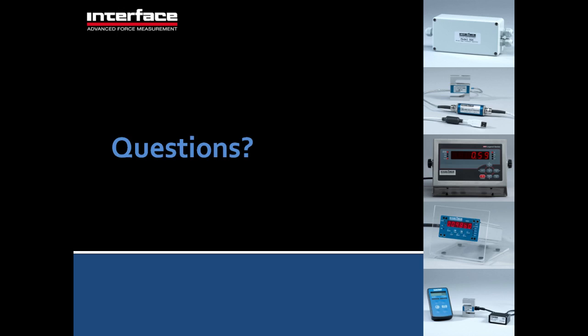And how do you know what sample rate is required? It's hard to say. Typically it's not going to be totally obvious, but typically you want the sample rate to be somewhere in the 7 to 10 times the event that you're trying to capture. So say you had something that's happening 10 times a second, you may need up to 100 samples per second for your sample rate. If that event, though, actually only takes a millisecond for each event, then you may need, say, 10,000 samples per second. So you really have to analyze what it is that you're trying to capture, and then how long does that event last, and then figure out the sample rate that's going to be somewhere in the 5 to 10 times faster than that.